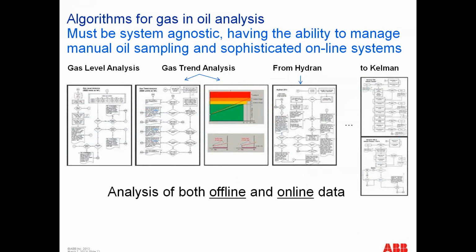And again, I want to emphasize online data needs to be accommodated at the frequency it comes in. Most of the DGA systems are taking samples on like a 4-hour basis, although many are user configurable. But this is done on many transformers today with whatever automated system.